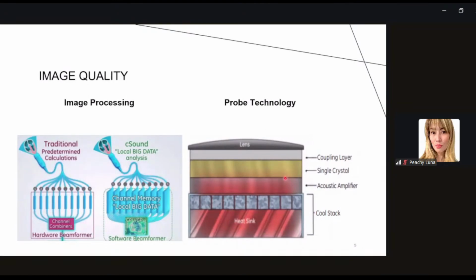Not only that, GE Healthcare came to introduce a new building block for the probes. They've added the acoustic amplifier layer right here and the cooling stack right here. So now we have three main elements: the single crystal, the acoustic amplifier, and the cooling stack. So what do they do? The single crystal is a highly efficient piezoelectric material that exhibits a wider bandwidth than conventional crystals. The acoustic amplifier, on the other hand, captures and then redirects the unused energy that passes through the crystals to enhance sensitivity and axial resolution, but most importantly, to increase and enhance penetration.